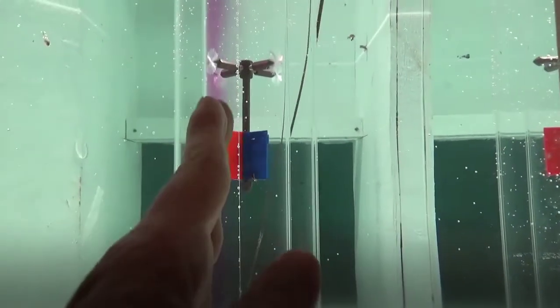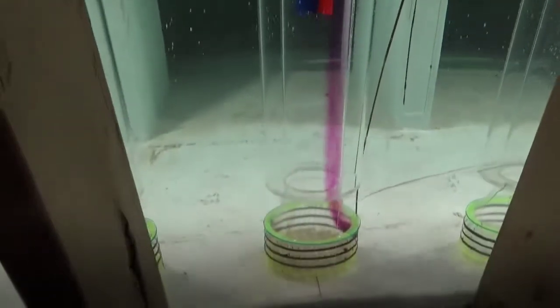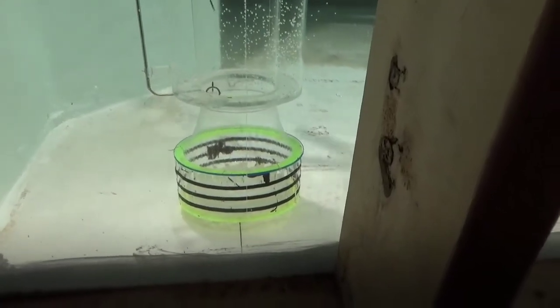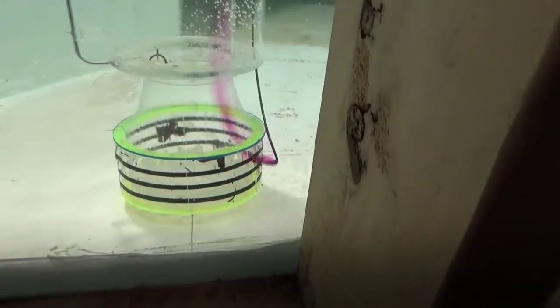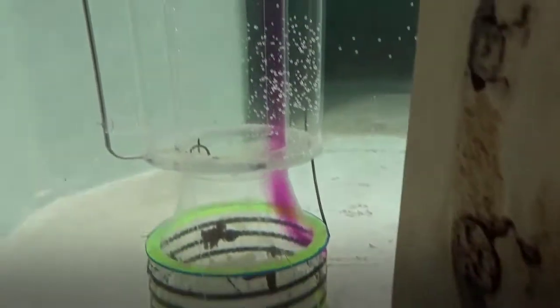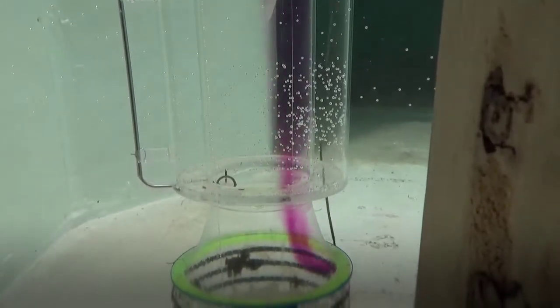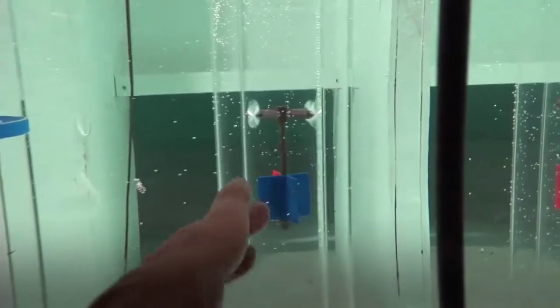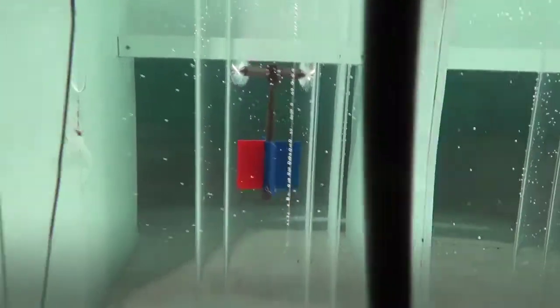That rotometer looks like it might just be a little bit crooked, and so that might even be why that's slowly rotating. Over on this one here, we've got nothing at all. You take a look at that one. You can see that dye just stays right attached. No rotation at all on that. So I think it looks like during the filling that one might have got slightly out of plumb, or out of round.